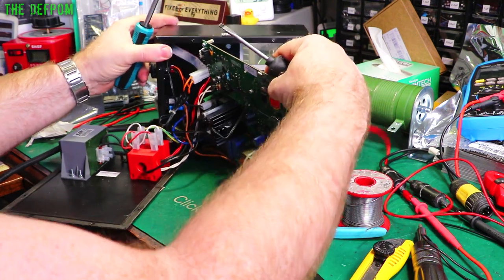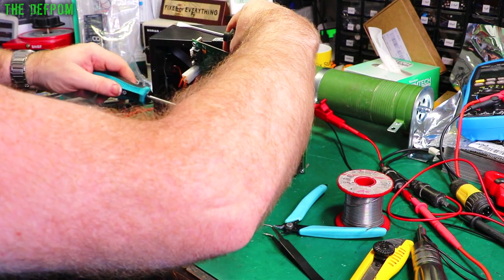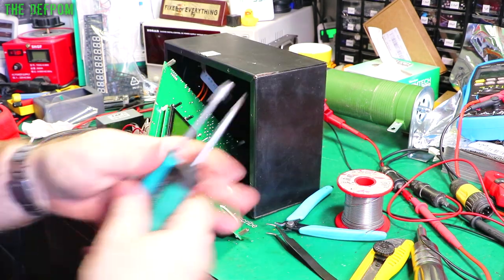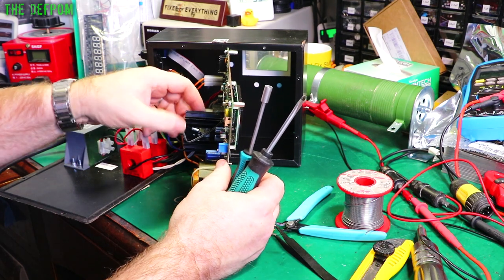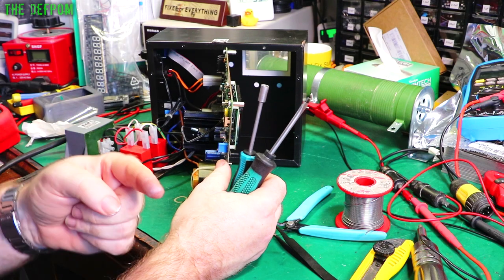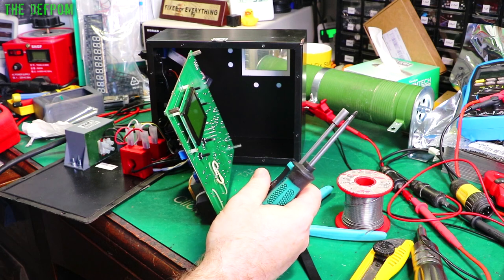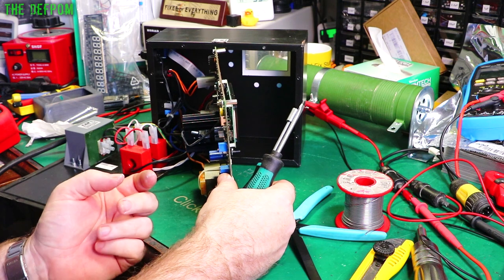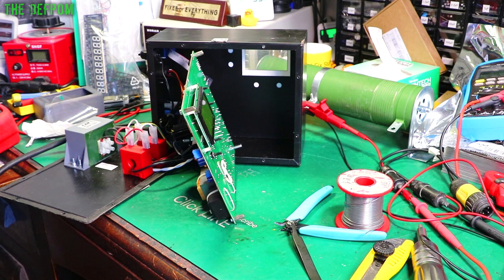I don't like having these wires all hanging off it but it's just unavoidable. I'll put that on with the right spanner. What I did actually find when I pulled this one apart is that the nut on this wasn't actually that tight - it didn't take much to shift it. On the other unit which I just repaired as well, when I first opened that one up, I did find that the sensor was actually loose - the bolt was just about to fall off. It'd come right undone. So it looks like it's maybe a common fault with these not being done up tight enough.